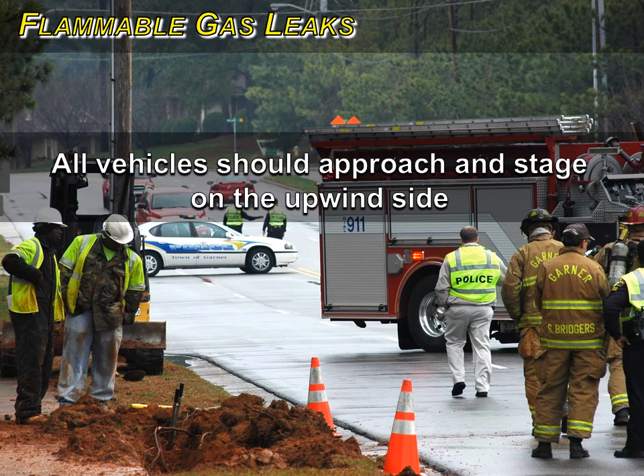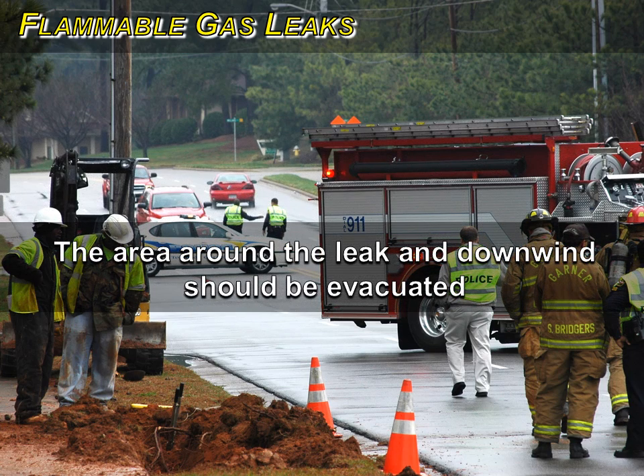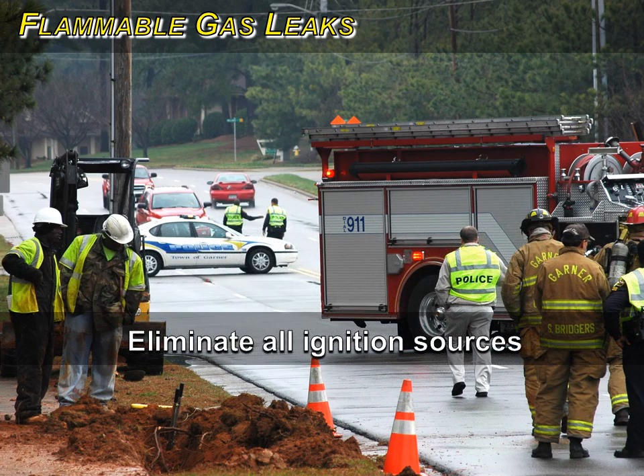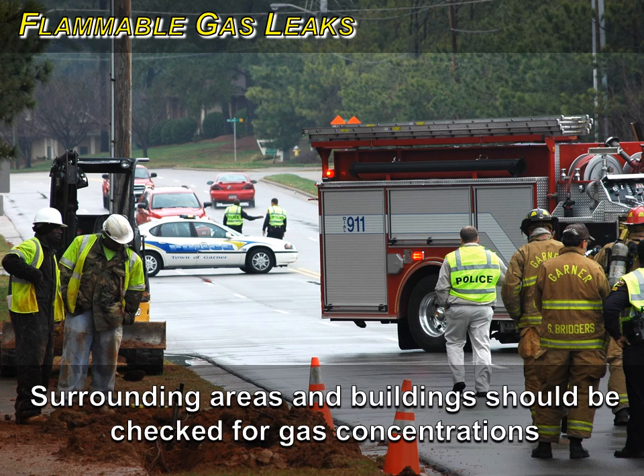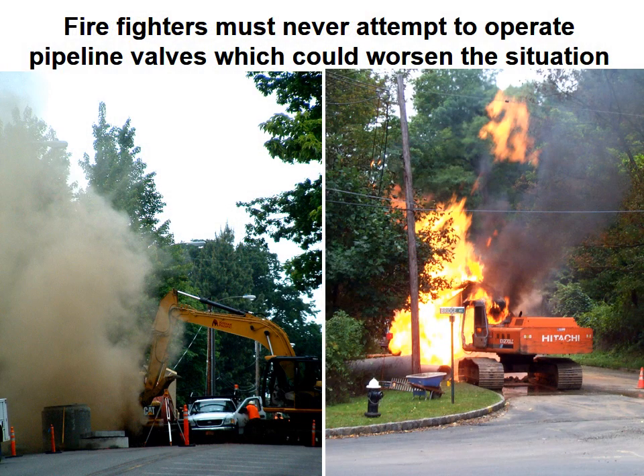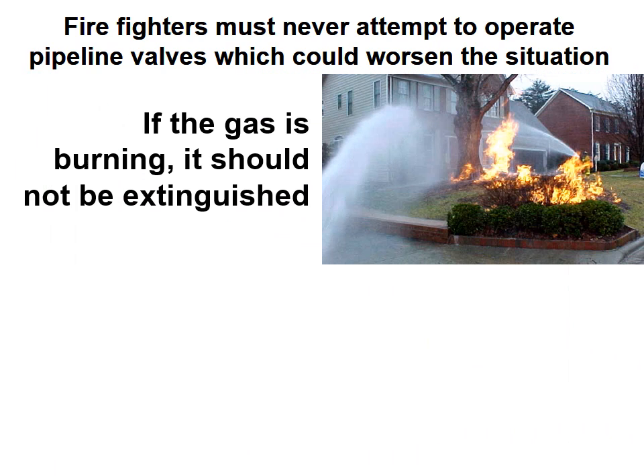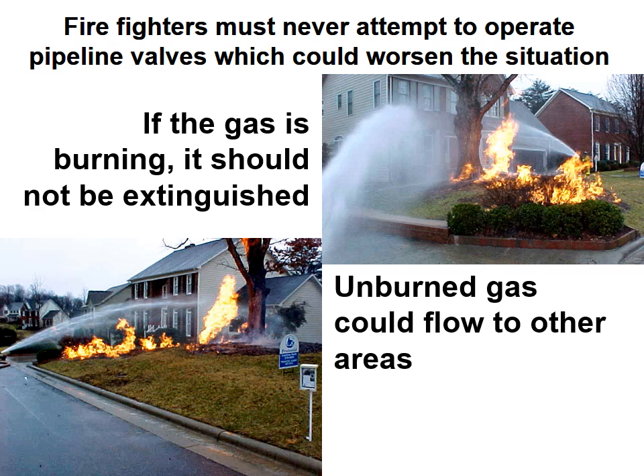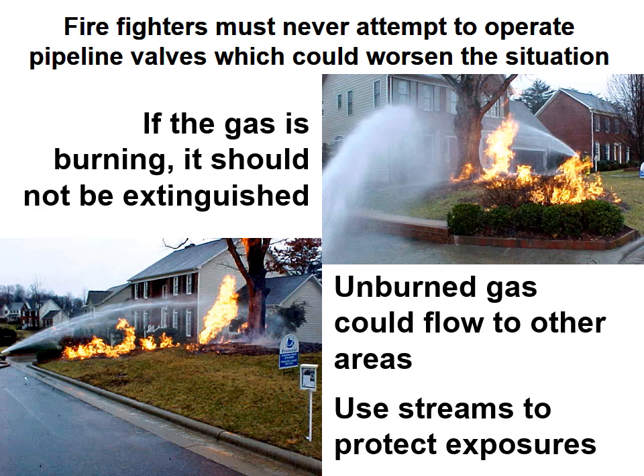Flammable gas leaks: contact the utility or pipeline company immediately for assistance. All vehicles should approach and stage on the upwind side. The area around the leak and downwind should be evacuated. Eliminate all ignition sources. Surrounding areas and buildings should be checked for gas. Firefighters must never attempt to operate pipeline valves, which could worsen the situation. If gas is burning, it should not be extinguished, as unburned gas could flow to other areas.